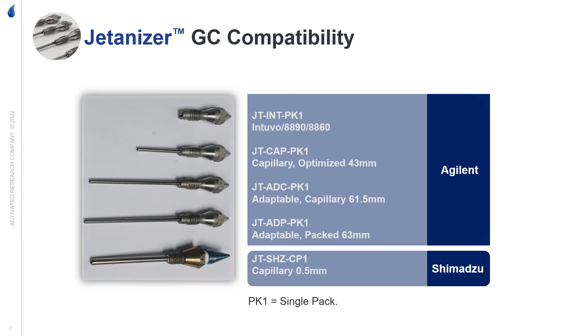The Jetanizer is compatible with Agilent 8890s, going all the way back to the 5890s, and Shimadzu 2030 and 2010 GCs. For an Agilent GC, it does depend on what type of FID connection is present.